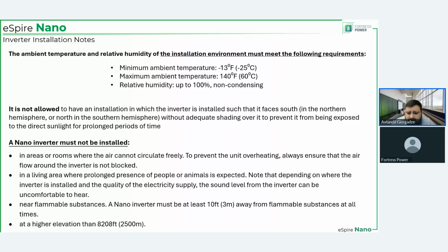If you are putting the inverter on the side of the outdoor battery unit, there is circulation for the inverter, right? There too, there are clearances, and we're going to get to that. But in any case, you should be mindful of the fact that this stuff is not liquid cooled and the cooling system is not somewhere else. The battery is equipped with an HVAC, and that itself needs some air circulation around it, and the inverter is air cooled, so air circulation is needed.